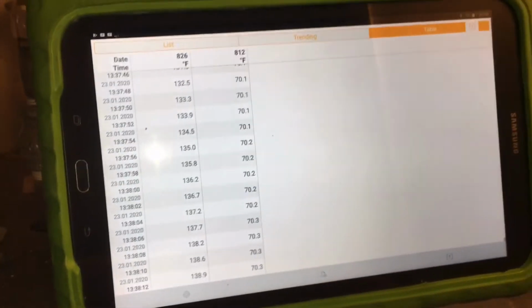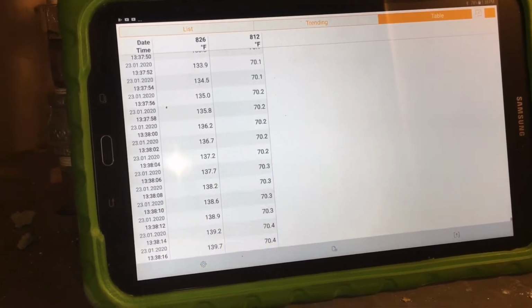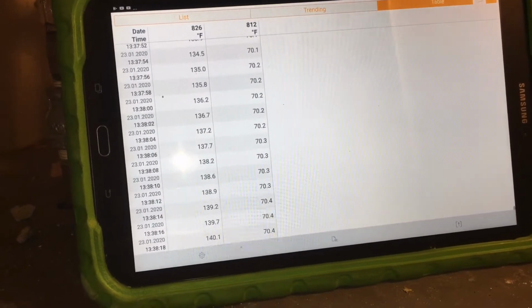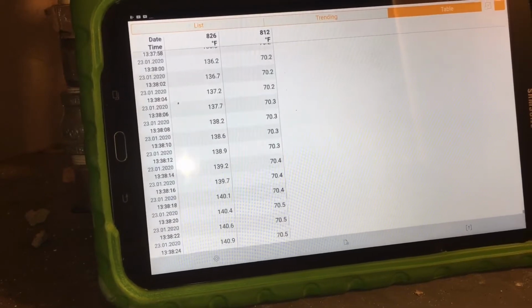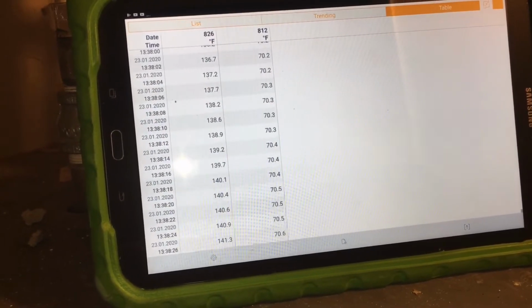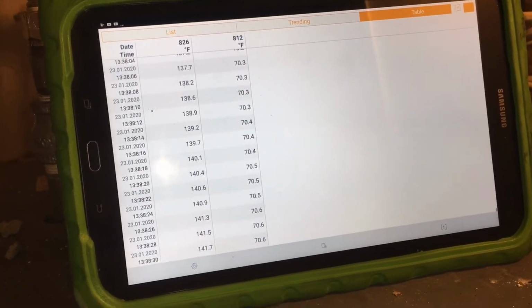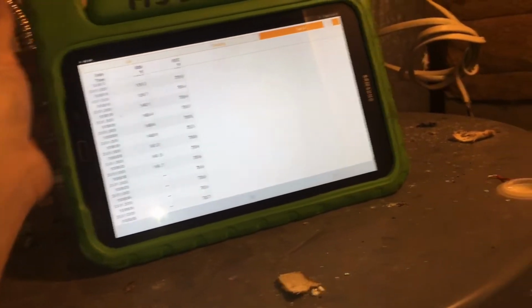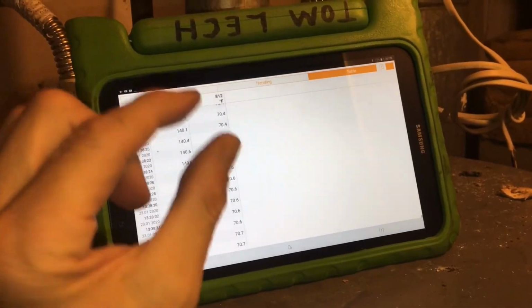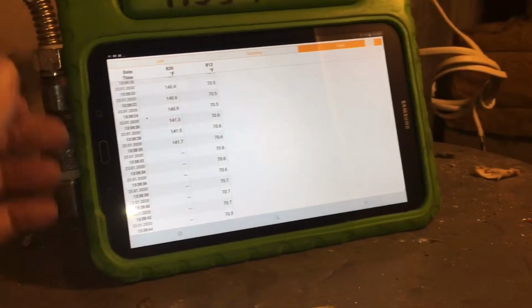The symptoms of this old furnace were, it would sometimes work only for a few minutes and shut off. Work for 30 seconds, shut off. Shut off for a while, and then maybe 3 minutes later, you would hear the engagement of the furnace, but before it ever even kicks on, it kicks off again, and you would continuously hear that. That was the contacts on the old Mercury having corrosion on them, not making good contact anymore, and kicking the furnace in and out.